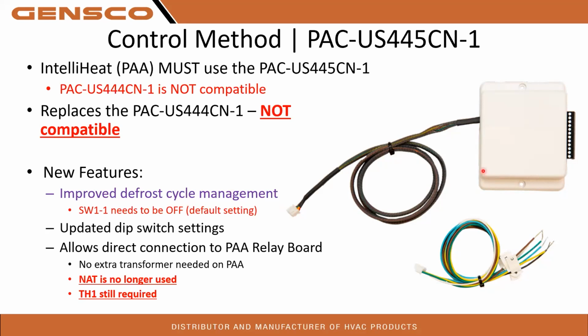The new 445 does have updated dip switch settings. So if you're used to using the 444s, make sure you read the installation manual on the dip switch settings because they have changed. You want to make sure that you're setting these things up correctly with the 445s. It allows direct connection to the PAA relay board, so you do not need a transformer on this one if you're using it on the PAA. It's going to steal power from the furnace. If you're using this, the non-adjustable thermostat is not needed because you have the 24-volt thermostat in its place. You still need that TH1 return air temperature thermistor. Got to have that one.